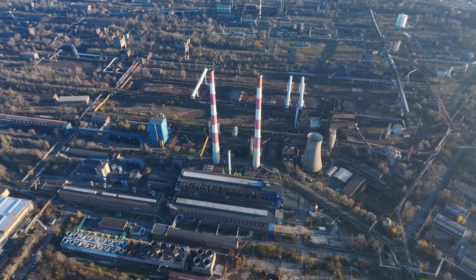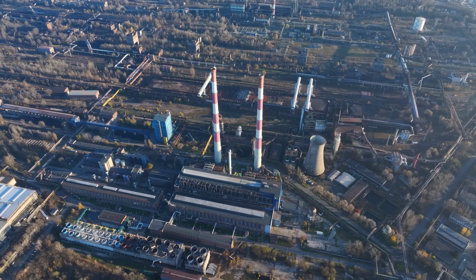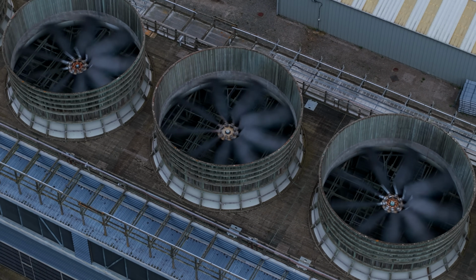With the VFD's ability to control speed, we're also able to start up a motor more slowly. Very large fan impellers with a huge diameter and a massive rotating inertia are very difficult for motors to start. I've seen motors take 20 to 30 seconds to start these large diameter fans up, whereas with a VFD, we can do that slowly. We can take minutes to start the same fan. And what that does is it reduces the electrical inrush, it reduces the mechanical shock on the system, and a bunch of other benefits as well.